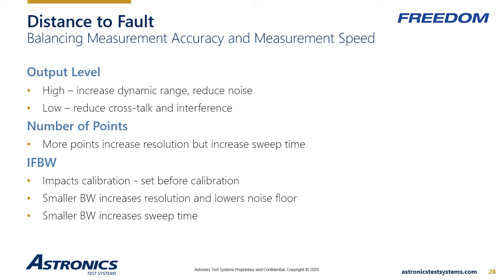Increasing the number of points swept by the VNA increases the resolution, but also increases the sweep time. The IF bandwidth should be set before sweeping, as any changes will require the VNA to be recalibrated. By decreasing the bandwidth, less noise is captured in the signal measurement, which effectively lowers the noise floor. The added resolution will make it possible to better distinguish between adjacent sweep points that might otherwise blend together. However, this increased resolution also comes with the cost of increased sweep time.